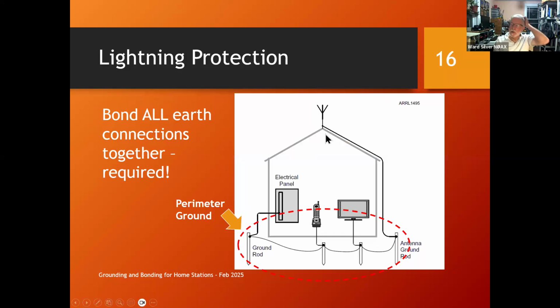Okay, let's go back to the perimeter ground. Here's the perimeter ground. It's got a ground rod. The ground rods are all connected together with heavy wire, like number 6 AWG. Number 6, number 6, number 6. All of these ground systems, your AC safety, your telephone, your cable TV, that antenna that you put on the roof that has the ground wire that NEC requires, all that goes down to a ground rod. You've got to bond all of these connections together.